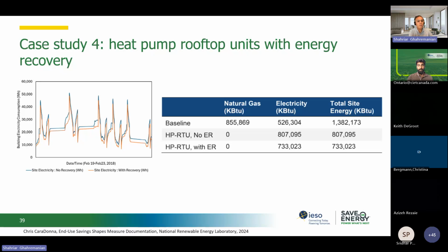If we have a natural gas burning rooftop, then in this real example it's around 850,000 kBTU of natural gas and 500,000 kBTU of electricity. So 1.3 million kBTU is the total energy. If we install a heat pump rooftop unit, for sure, zero natural gas, and the electricity use will go higher. It becomes 800,000 kBTU. That's going to be the only energy that we need. If we install a heat pump rooftop unit with energy recovery, then that 800 goes down to 730,000, and that's going to be much less energy use.